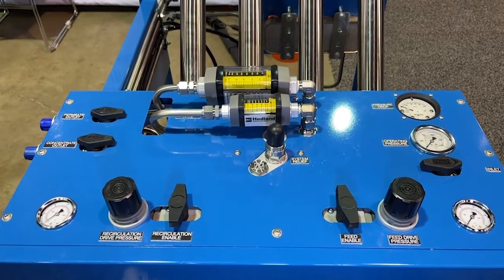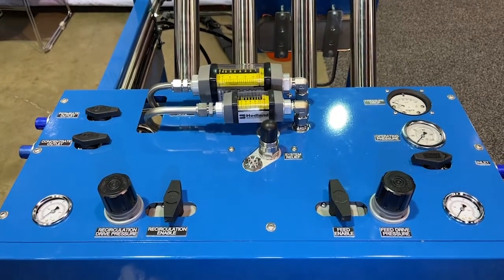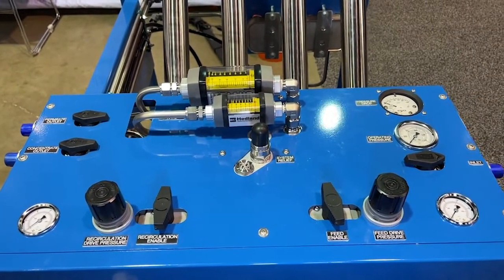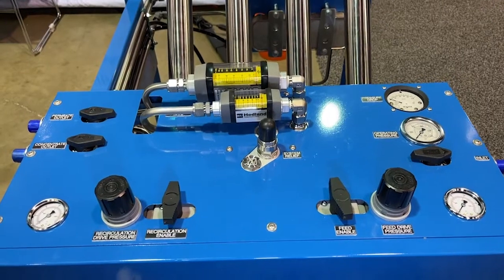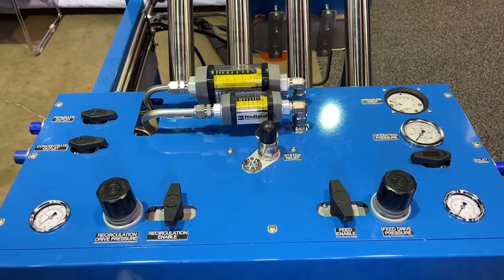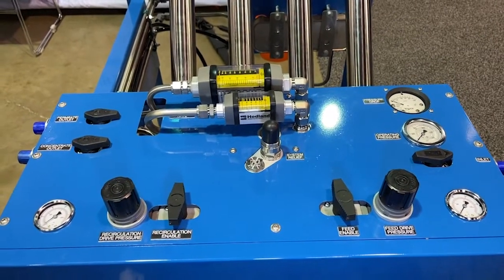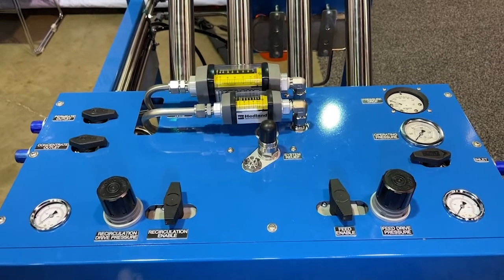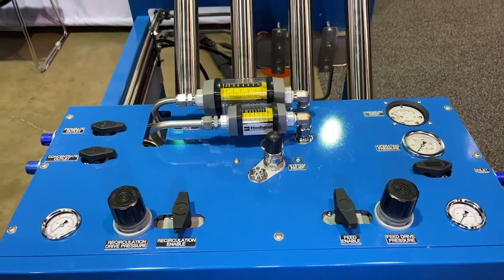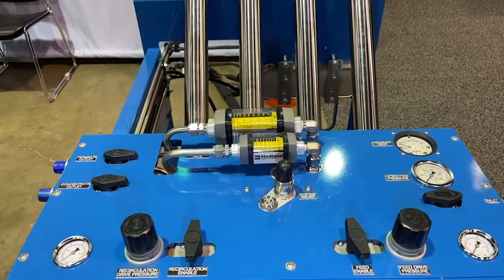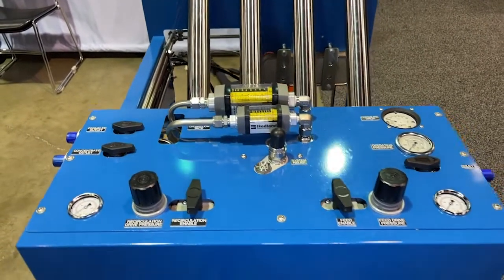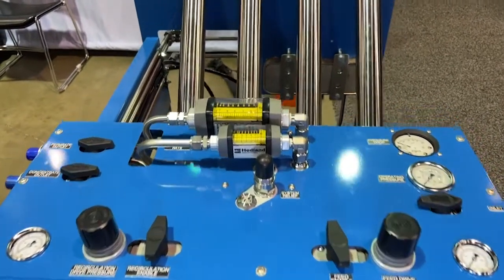That 2-to-1 ratio then proceeds to either a rotary evaporator, a falling film evaporator if you've already got one, or even a decarb vessel if your operation is small enough, if your batches aren't so big. Typically you can just strip the residual solvent in a decarb and then decarb after that, so you don't have to bother with it anymore.